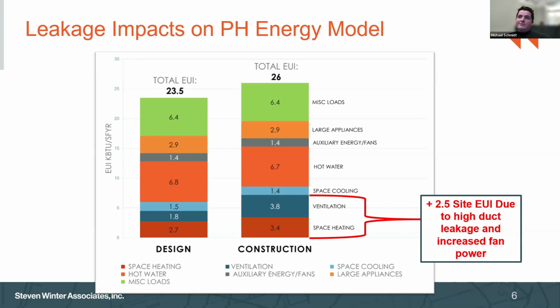But I think I'm showing here another point: Passive House does a great job at reducing our heating and cooling loads to a very low level. The big assumption is then that hot water becomes a larger chunk of that energy pie. But I think this graphic also shows that ventilation can start to encroach and take up a larger portion of that energy pie if it's not installed correctly and we do not have adequate duct sealing.